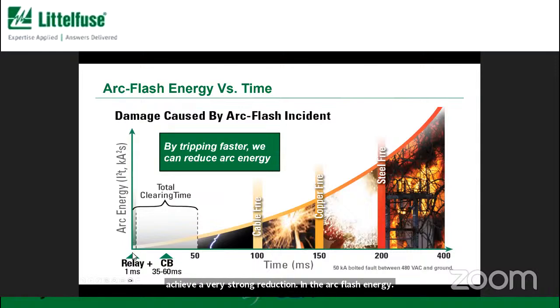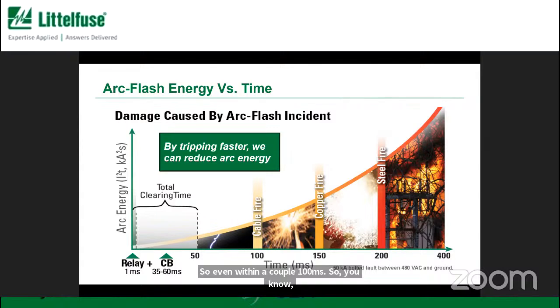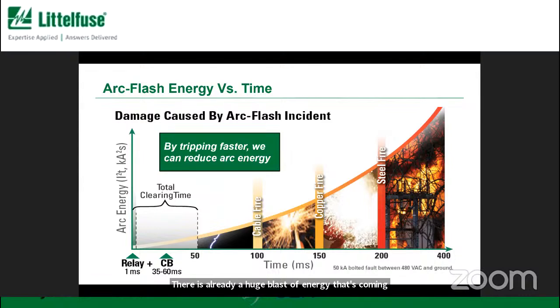So when we have an arc flash, the amount of energy that comes out rises very, very quickly. Even within a couple hundred milliseconds, so in the amount of time it takes to blink your eye, there is already a huge blast of energy coming out. So the way that we can reduce that energy is by shutting down the system as fast as possible. These arc flash relays are able to see the arc and provide a tripping signal to the circuit breaker in less than 1 millisecond. So that is very, very fast.